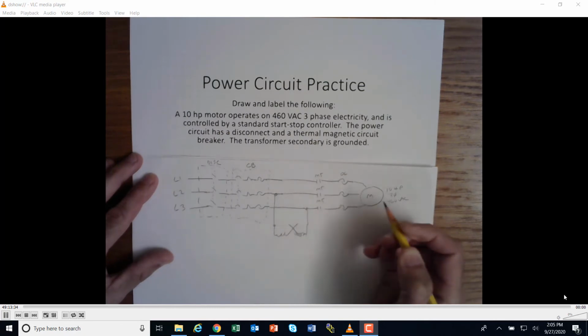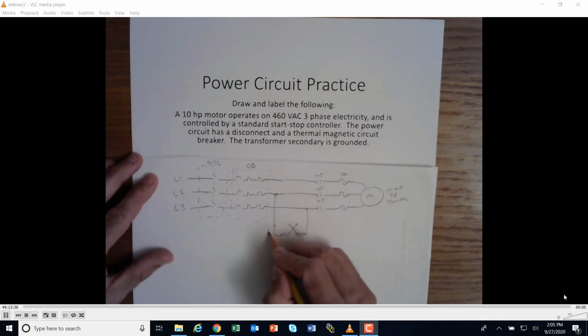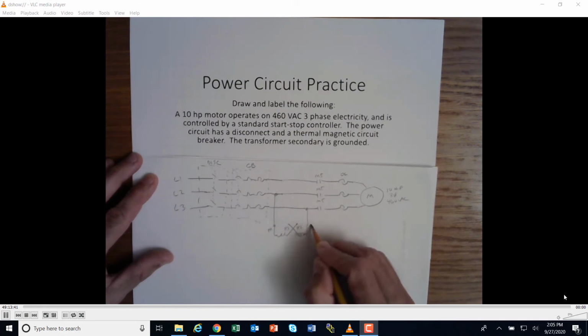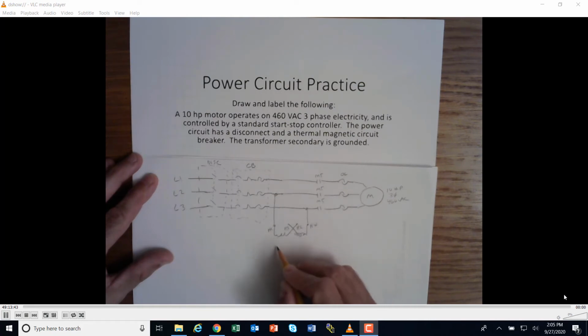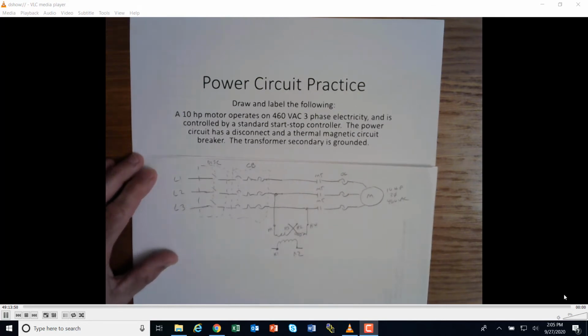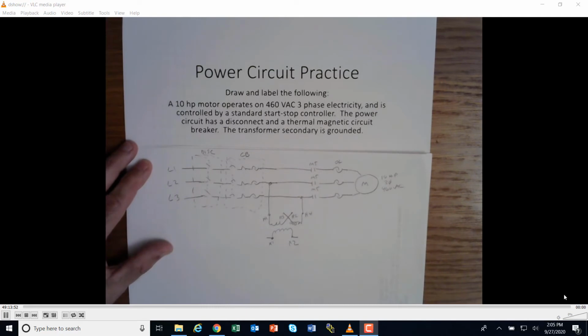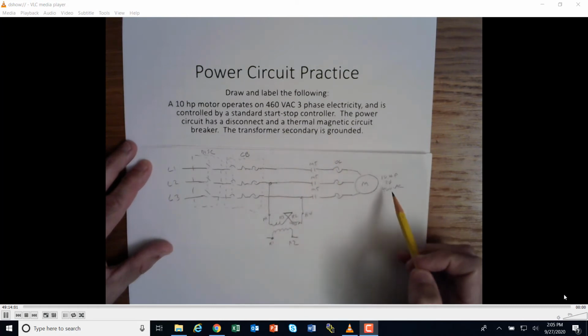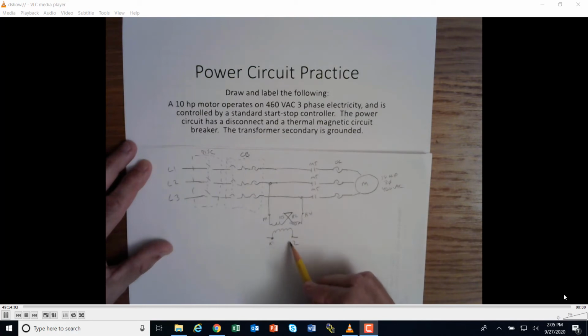like this. And we'll go ahead and go H1, H3, H2, H4. And on this side, X1, X2. Okay. Now I'm doing a 4-to-1 step down because we have high voltage. So I've got to put them in series right there. And that's going to step that down from 460, 4-to-1. I'm going to have 115 on this side, which is great control voltage.